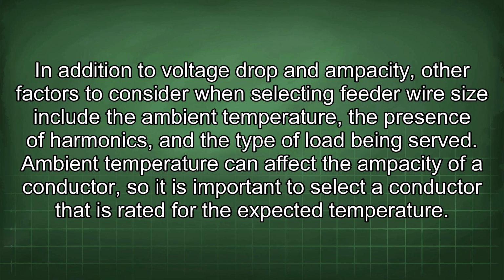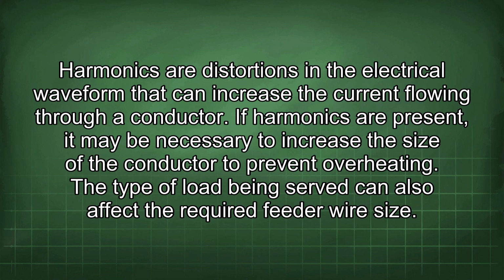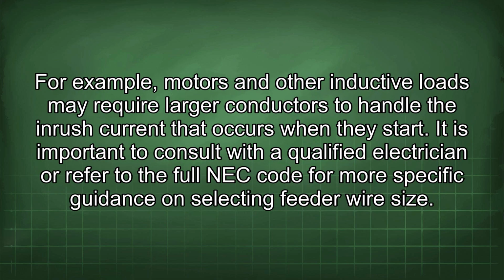In addition to voltage drop and ampacity, other factors to consider when selecting feeder wire size include the ambient temperature, the presence of harmonics, and the type of load being served. Ambient temperature can affect the ampacity of a conductor, so it is important to select a conductor that is rated for the expected temperature. Harmonics are distortions in the electrical waveform that can increase the current flowing through a conductor. If harmonics are present, it may be necessary to increase the size of the conductor to prevent overheating. The type of load being served can also affect the required feeder wire size. For example, motors and other inductive loads may require larger conductors to handle the inrush current that occurs when they start.